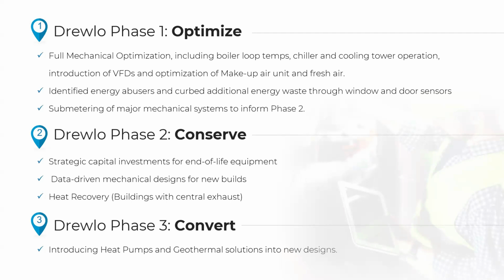Mechanical equipment in commercial buildings has a minimum life cycle of 20 years. That implies that for virtually all existing buildings, we're only going to get one more chance to touch the mechanical system when end of life comes up, whether that's 2, 5, or 10 years from now. If we don't use that opportunity, we'll lock ourselves in for another 20 years, because under almost no scenario would it make sense to do a like-for-like replacement at the mechanical plant level, like putting in new boilers and then ripping those out 5 to 10 years down the road, less than halfway through their life cycle.